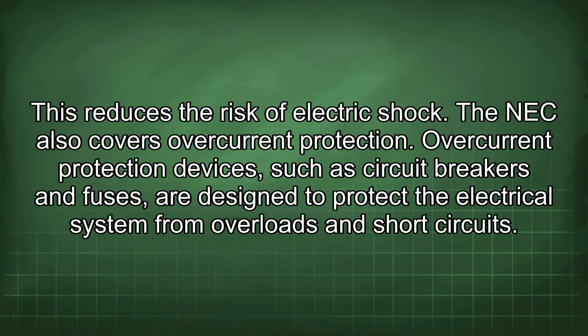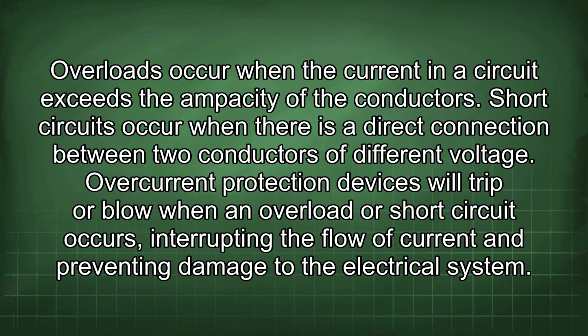The NEC also covers overcurrent protection. Overcurrent protection devices, such as circuit breakers and fuses, are designed to protect the electrical system from overloads and short circuits. Overloads occur when the current in a circuit exceeds the ampacity of the conductors. Short circuits occur when there is a direct connection between two conductors of different voltage. Overcurrent protection devices will trip or blow when an overload or short circuit occurs, interrupting the flow of current and preventing damage to the electrical system.